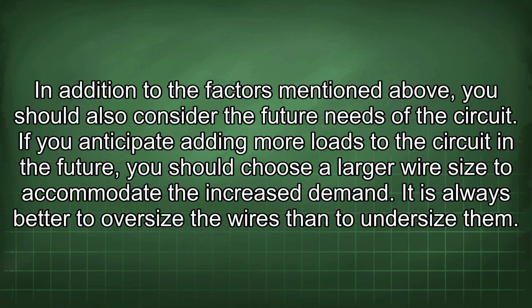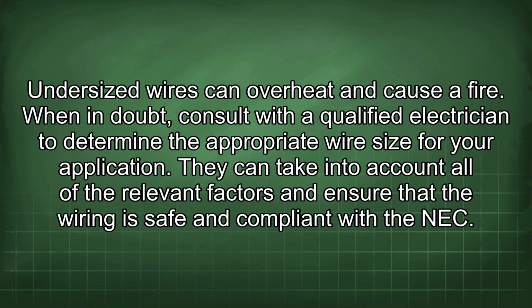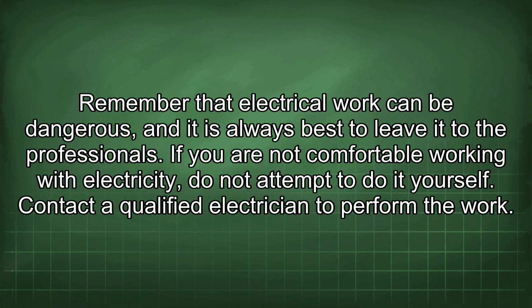In addition to the factors mentioned above, you should also consider the future needs of the circuit. If you anticipate adding more loads to the circuit in the future, you should choose a larger wire size to accommodate the increased demand. It is always better to oversize the wires than to undersize them. Undersized wires can overheat and cause a fire. When in doubt, consult with a qualified electrician to determine the appropriate wire size for your application. They can take into account all of the relevant factors and ensure that the wiring is safe and compliant with the NEC. Remember that electrical work can be dangerous, and it is always best to leave it to the professionals.